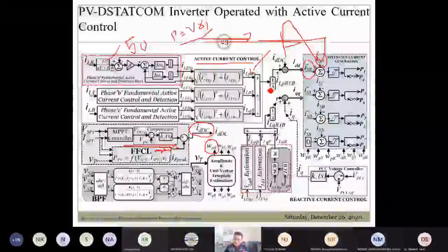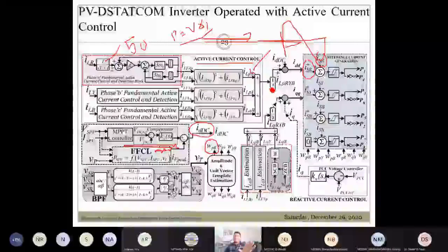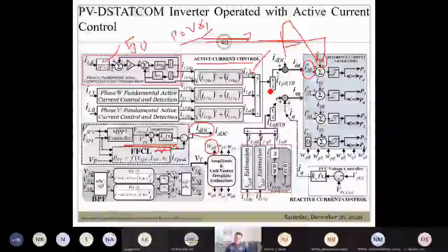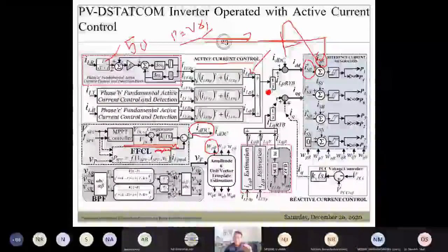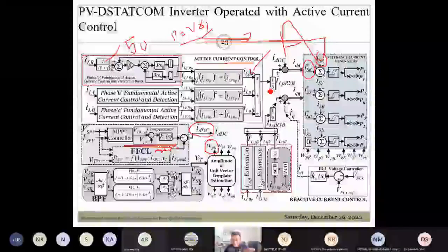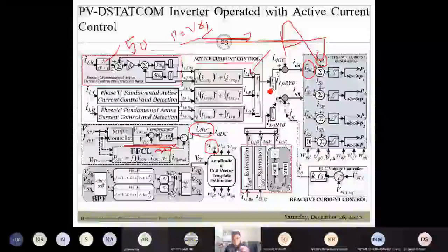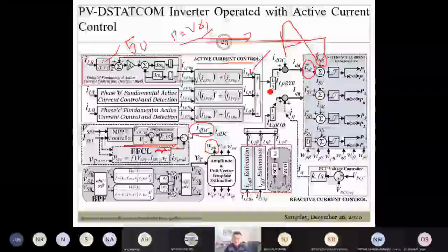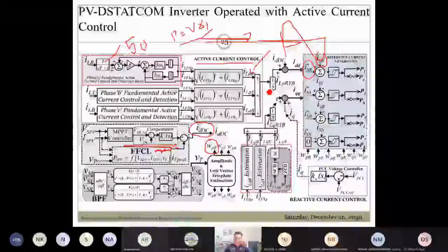So what they have done is they have asked these PV inverters to stay connected, but not to inject any amount of active power or reactive power. If the voltage sag is well within the acceptable threshold, or well within the reactive current capability of the inverter, then in that case this inverter will provide the reactive power support, and the voltage sag can be compensated.